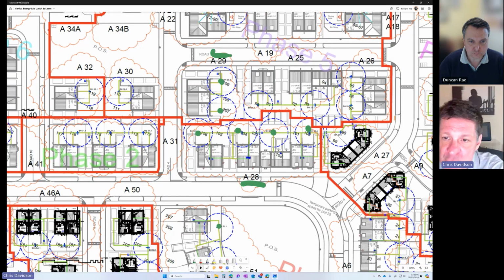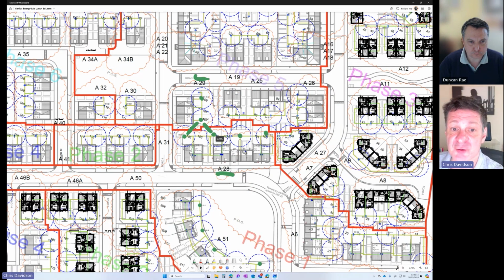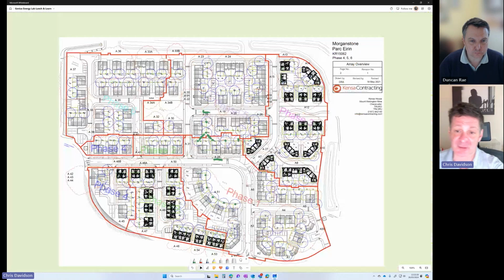Now, while those are not hydraulically connected to each other, they are actually close enough to be in thermal contact. So when designing a system like this, we can't just look at each individual dwelling. We've got to think about how those individual arrays interact with each other. That gives you a snapshot of how we do the design, both hydraulically and space dependent.